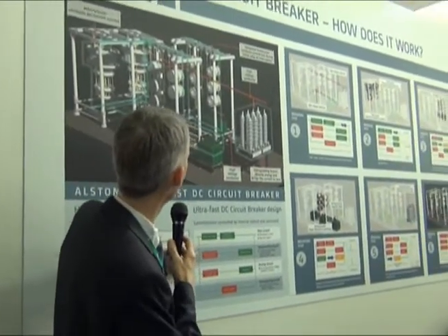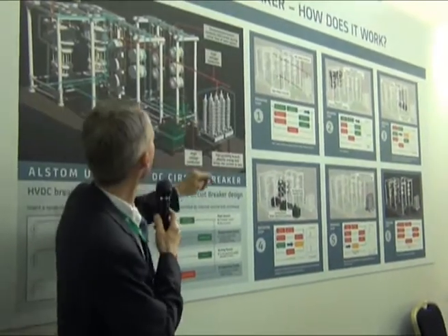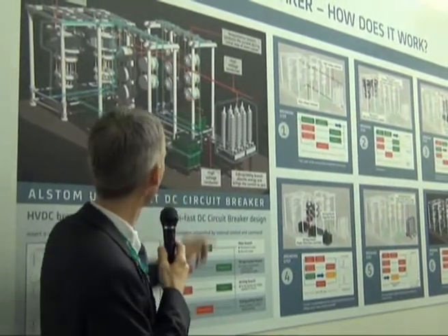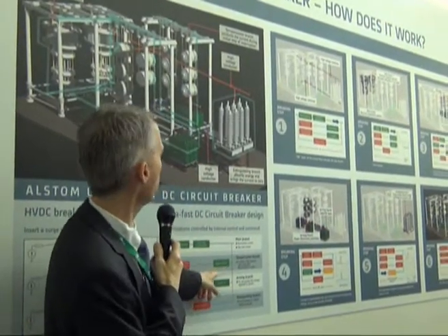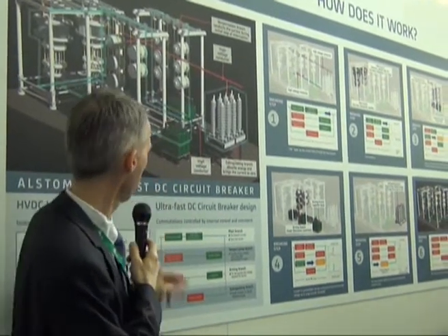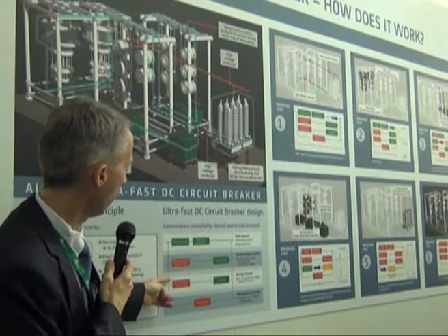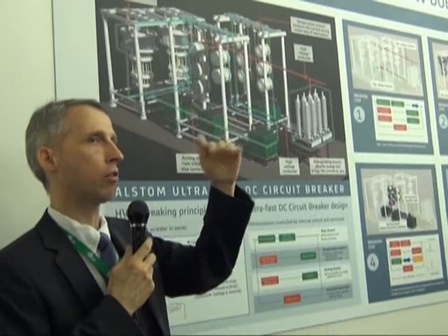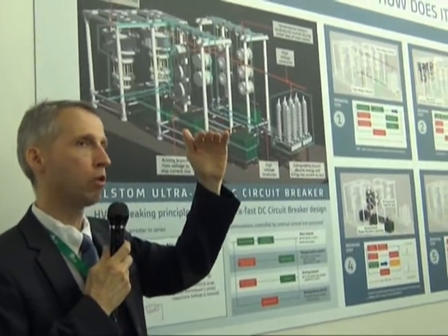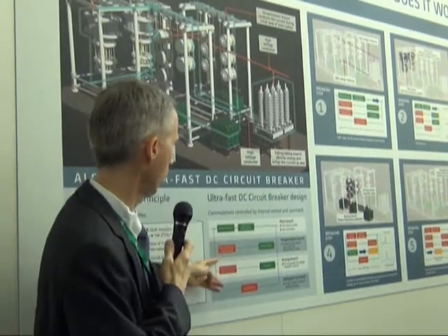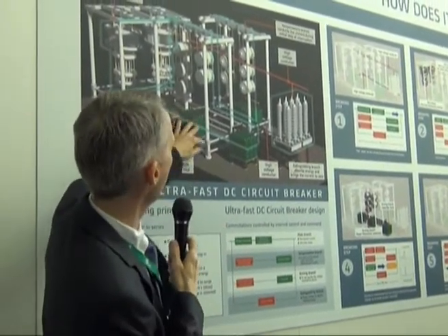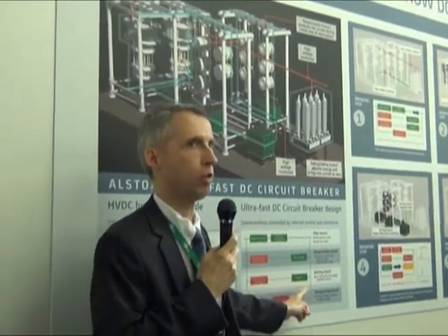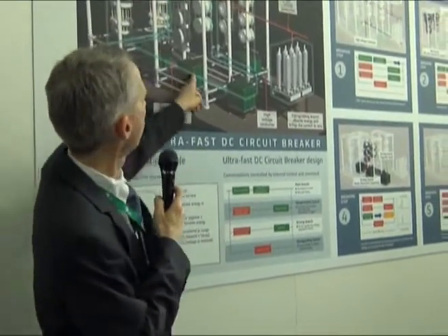Going back to this temporization branch, there's the chassis in the back. These thyristor-type power electronics are these stacks that are hanging here. The surge arrestor and capacitor are those over here. The next branch here, the arming branch, is the one that raises the voltage, starts opposing or exceeding the voltage of the network, which means you stop the current from rising. This is a very important function. That's the chassis here in the front, and this capacitor here has to withstand the full voltage of your network, which means you need a bit more in series.